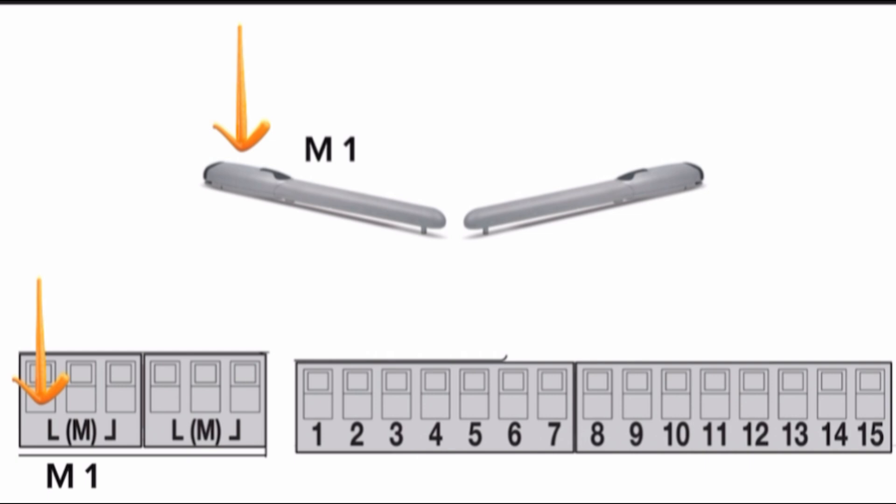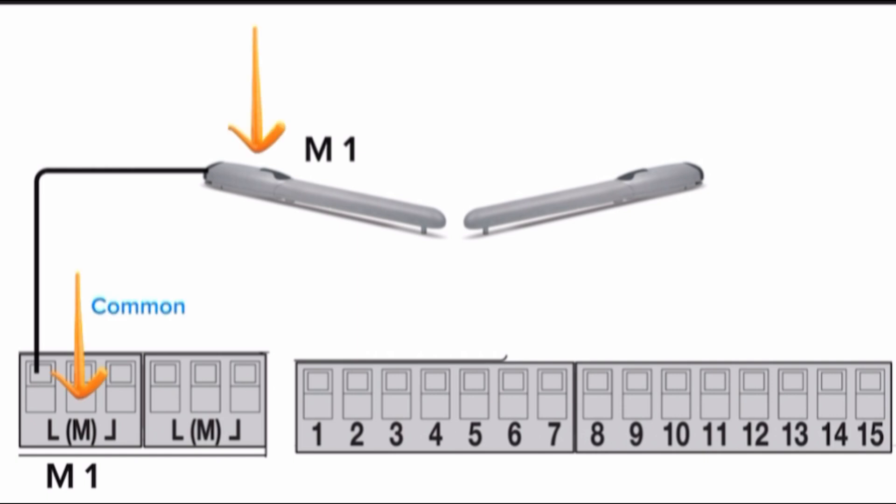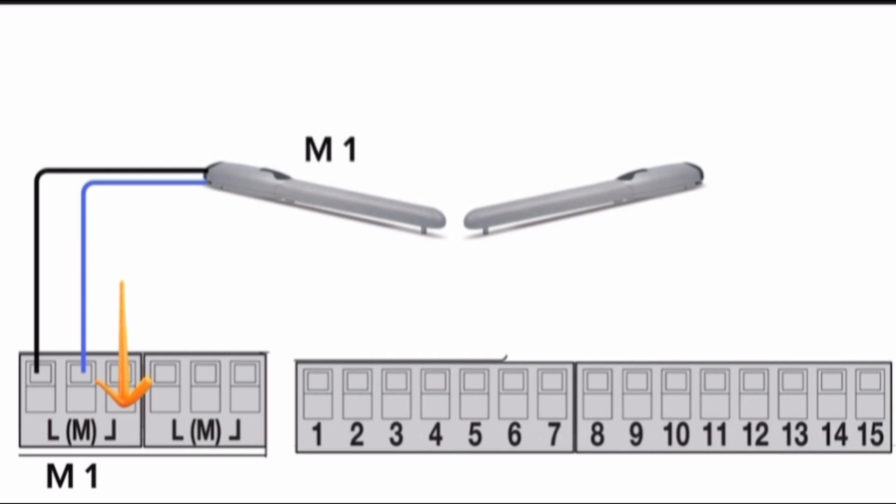Please connect motor 1. The M terminal of motor 1 block is the common or negative for motor 1. Please connect the motor 1 common wire in the control board to terminal 2. The second L terminal of motor 1 block is giving power supply for closing the motor. Please connect the motor 1 phase closing wire in the control board to terminal 3.